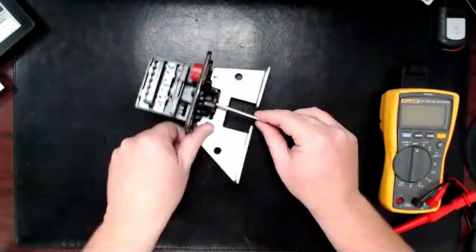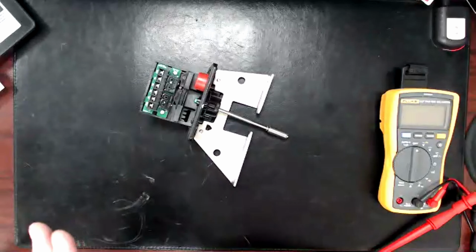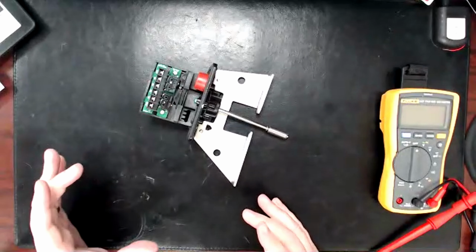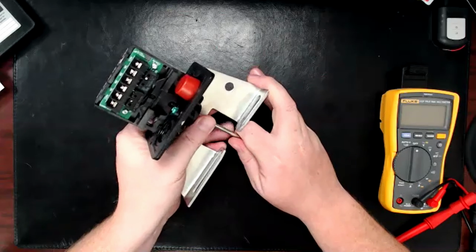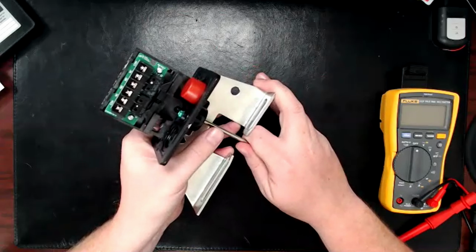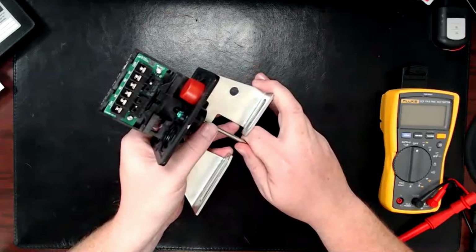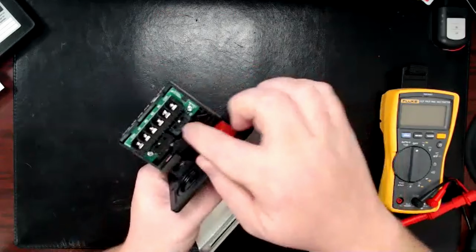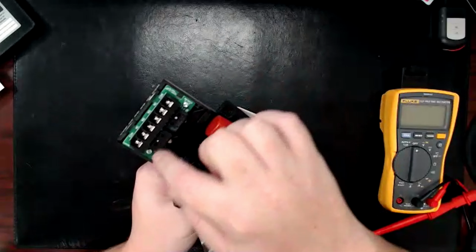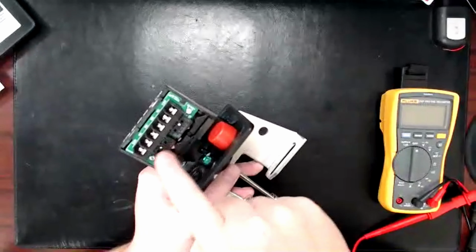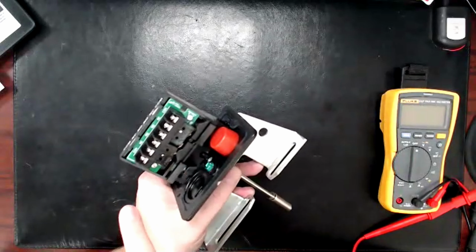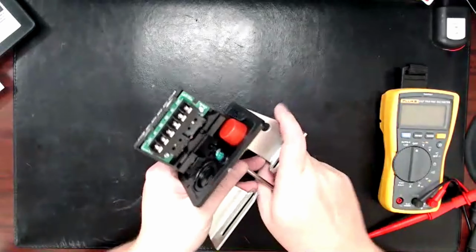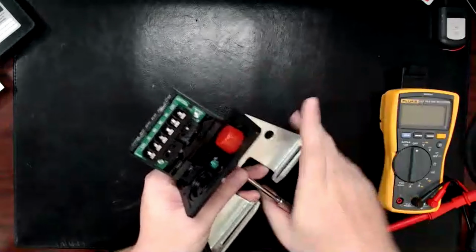And so there's some adjustment where you take the face off the valve and you spin the block down the threads, and you get it so that it's set just right to where it's holding it right there where it needs to be while the valve's all the way open. And then as you crank it in, it releases that switch. So this little black part right here, and there's a second one here, are your actual switches. And then these are just terminals to make it easier to wire onto the switch. And everything else is about activating that little orange button.